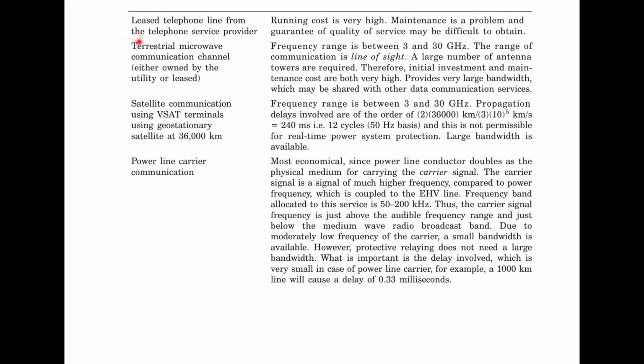Second is the terrestrial microwave communication channel, either owned by the utility or leased. The frequency range is between 3 to 30 gigahertz. The range of communication is line of sight, so a large number of antenna towers are required. Therefore, initial investment and maintenance costs are both very high. It provides a very large bandwidth which may be shared with other data communication services.